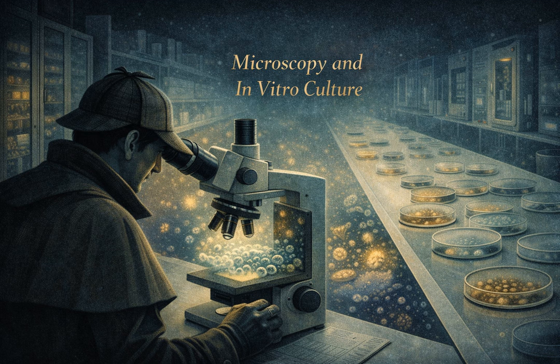And this is where the famous oil immersion technique comes in. I still remember doing this in my first micro lab, putting that little drop of sticky oil right on the cover slip and carefully lowering the 100x lens right into it. It feels so counterintuitive, doesn't it, to deliberately smear oil all over a very expensive lens. But the physics behind it is, frankly, brilliant. Immersion oil has been engineered to have a refractive index of about 1.51. Which is almost exactly the same as glass.